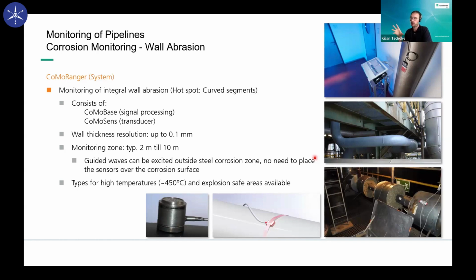If you remember, there's a relationship between frequency, wall thickness, and velocity of the waves. You can fix the frequency, since it's a parameter of your setup and hardware, and fix the distance between your sensors. Then, by measuring the time of flight between two sensors, you can calculate the wave velocity between them. Using the relationship between velocity, frequency, and wall thickness, you can recalculate the wall thickness of the pipe in that section. This is the easiest case of a sensor system: sensors, measurement hardware, and a monitoring zone for corrosion.